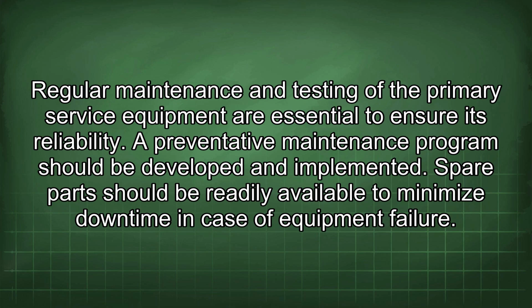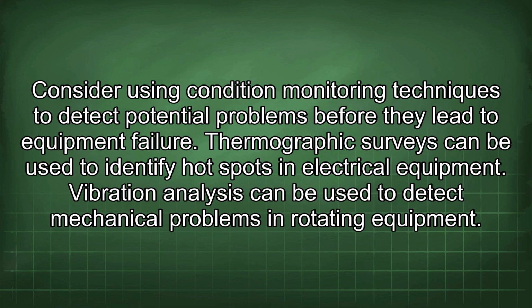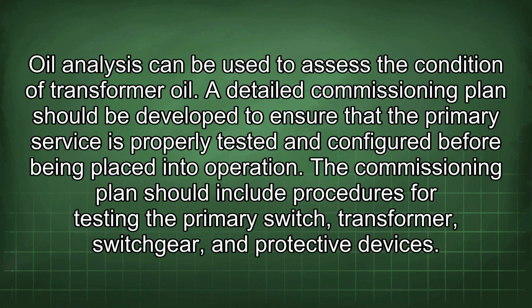Spare parts should be readily available to minimize downtime in case of equipment failure. Consider using condition monitoring techniques to detect potential problems before they lead to equipment failure. Thermographic surveys can be used to identify hotspots in electrical equipment. Vibration analysis can be used to detect mechanical problems in rotating equipment. Oil analysis can be used to assess the condition of transformer oil.